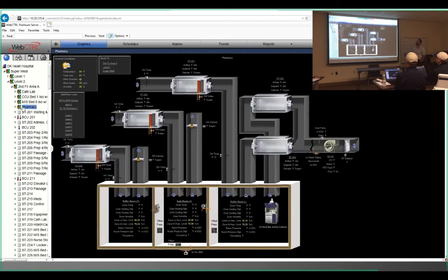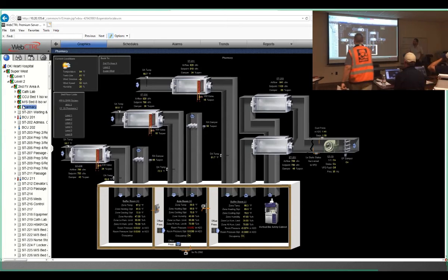So, yeah. This is all of that graphic on your graphics, right? You see down below, you've got the buffer room, the ante-room in the middle, and then the positive buffer room and the negative buffer room. Those are being controlled by the 3 VAVs and then 2 exhaust terminal units that are hooked up to exhaust fans. So go ahead, Michael, show them a little more.